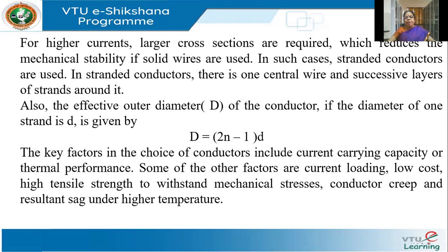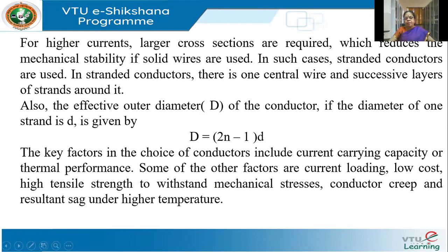Normally in a stranded conductor, you have a central wire and successive layers of strands around it. If the diameter of one strand is d (lowercase), then the effective diameter D is given by: D = (2n − 1) × d, where n is the number of layers of strands.